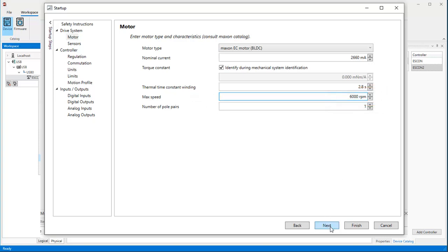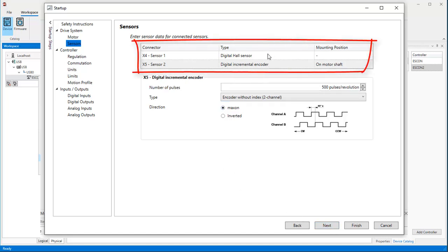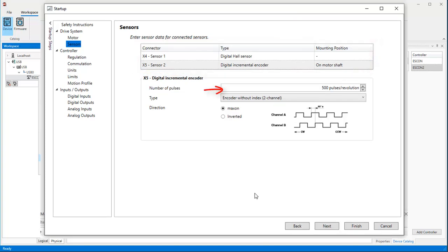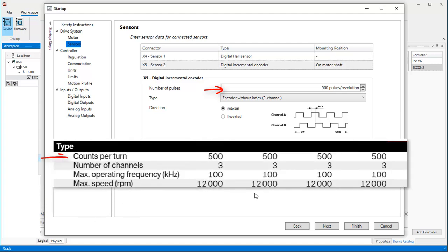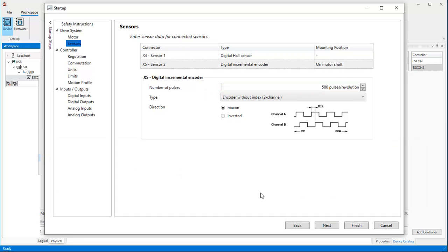Press Next to get to the sensor specification. We have digital hall sensors and a digital incremental encoder on the motor shaft. Define the resolution of your encoder in pulses or counts per revolution. Again, the value can be found in the corresponding encoder specification, and it's a pre-quadrature value. Hence, the actual resolution is 4 times higher. Press Next.